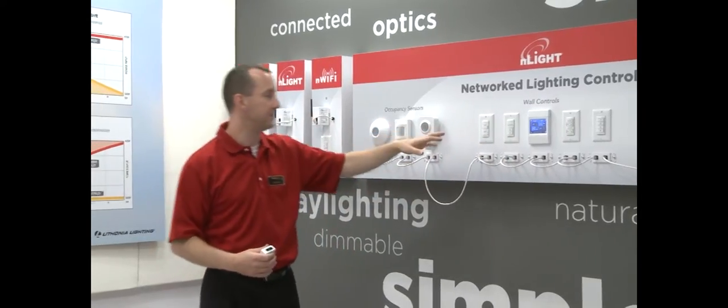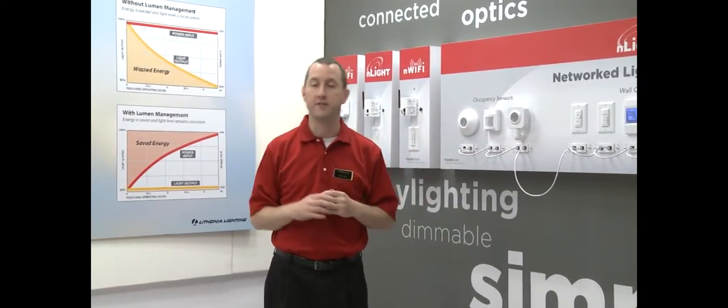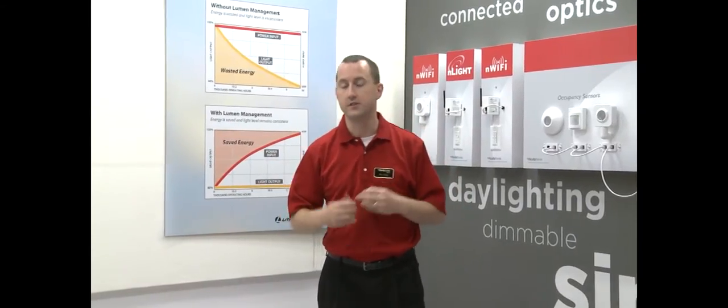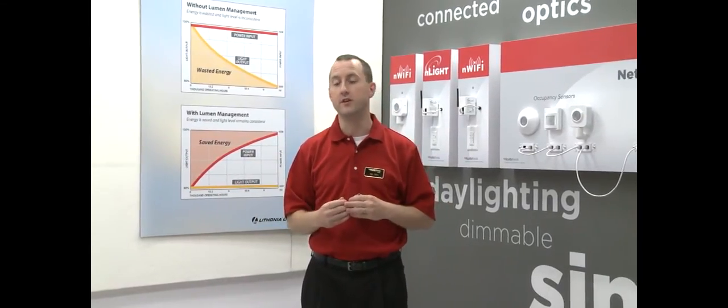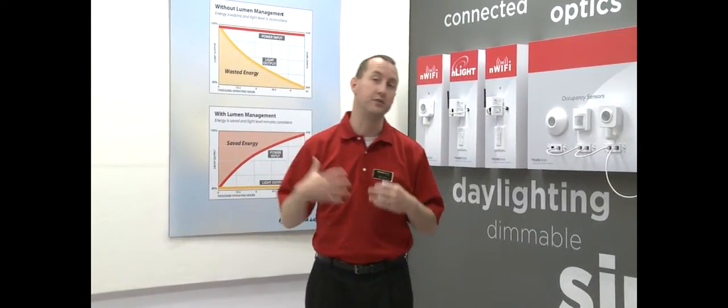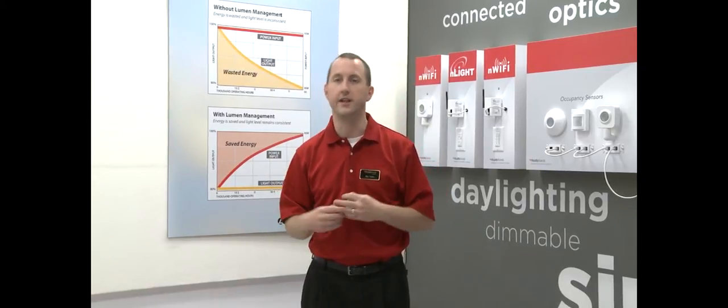All these devices are powering off of the bus power provided by the fixture. So from a labor standpoint, there's significant savings because your contractor's not having to run any extra power wires to any control devices. They're only running the power wires to the fixtures, which they would have been doing anyway.